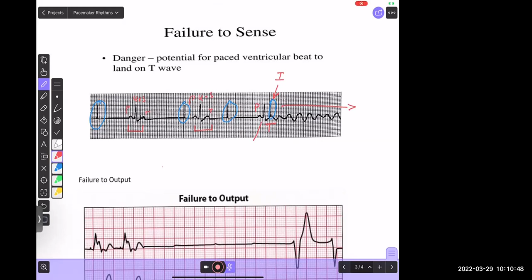It happened to land on the, so here's the P wave, here's the QRS complex, here is the T wave. That pacer spike just happened to land on the T wave and cause an R on T phenomenon and cause that patient to deteriorate into ventricular fibrillation. So this pacemaker actually caused an R on T phenomenon. Clearly, this pacemaker is not sensing the patient's underlying cardiac activity. Otherwise, it would be able to sense and inhibit. It should be inhibiting itself. It should be like, hey, don't fire, particularly don't fire on the T wave. And so this is what we call failure to sense. And the life-threatening complication of a failure to sense is that it happens to fire on the T wave and cause R on T phenomenon.